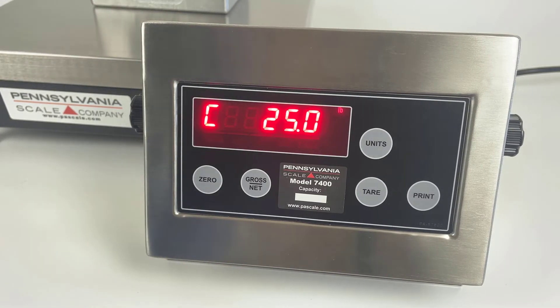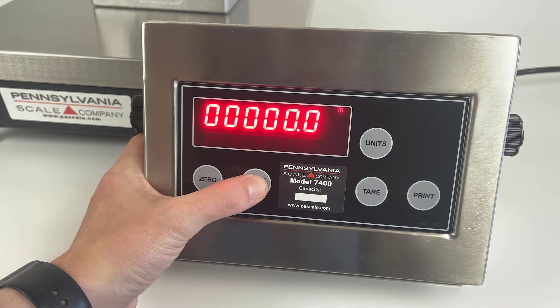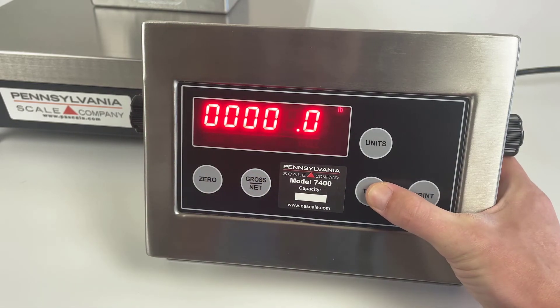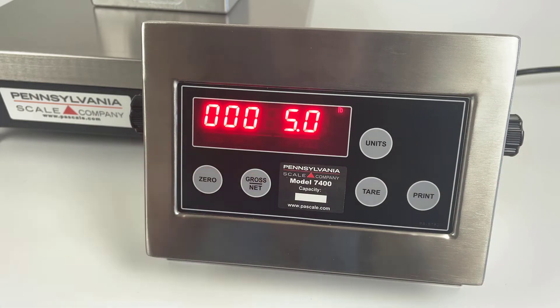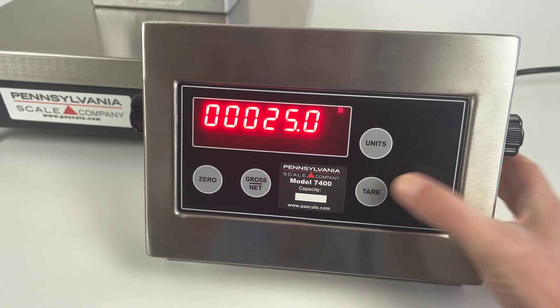Next, place your weight on the scale. It shows you a live reading. If it's incorrect, use the gross/net key to select the tens place and the tare key to increase the value. The print key then confirms, and the dashes show that it's calibrating.